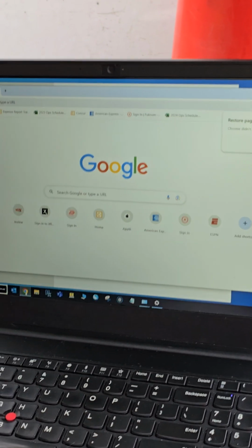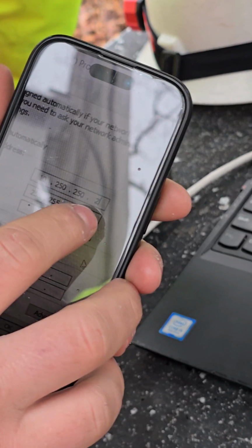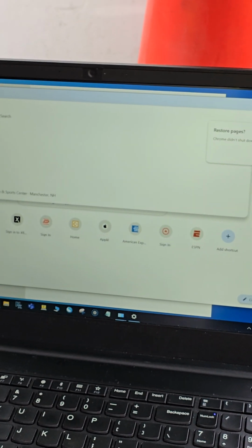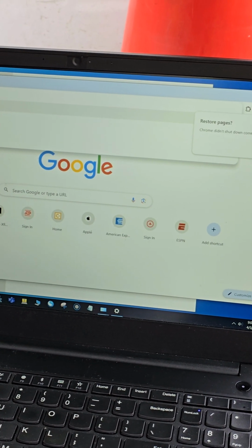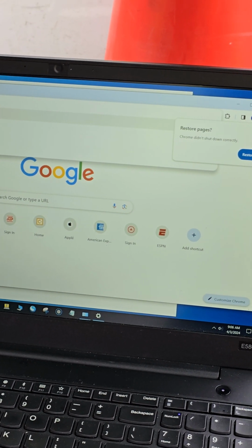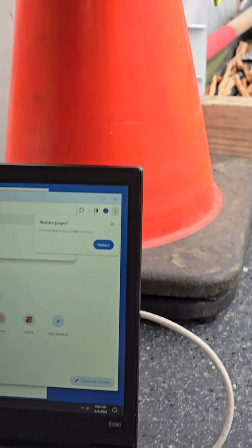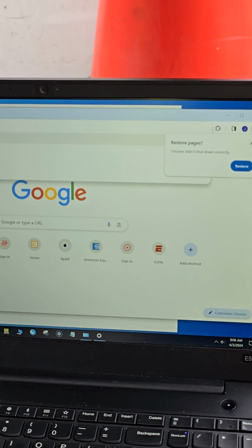And then I entered in, as you can see, 10.250.250.2, the last digit. The last digit you always want to be either one higher or one lower than the actual IP address, because the actual IP address to log in is .1. So you enter it on your computer either .2 or .0. Because if you do .1, you can't set the IP address to the computer and then log into the same IP address. So it just needs to be one off, that's all.